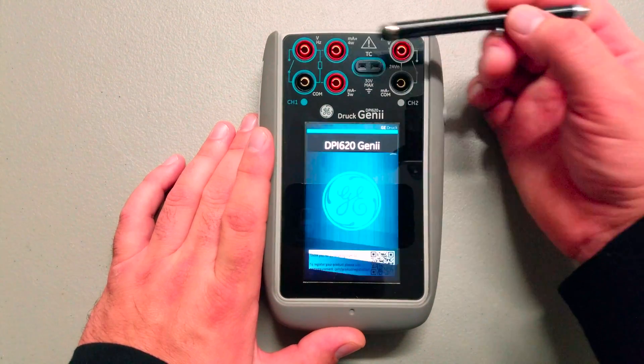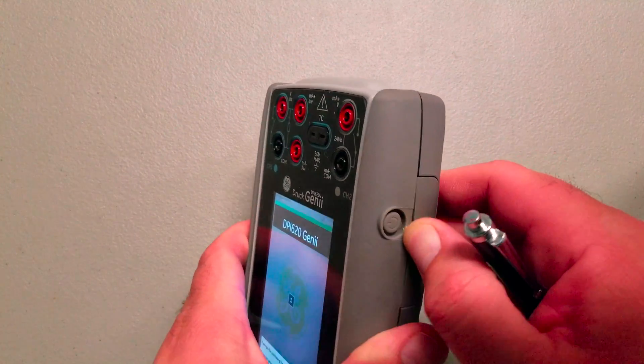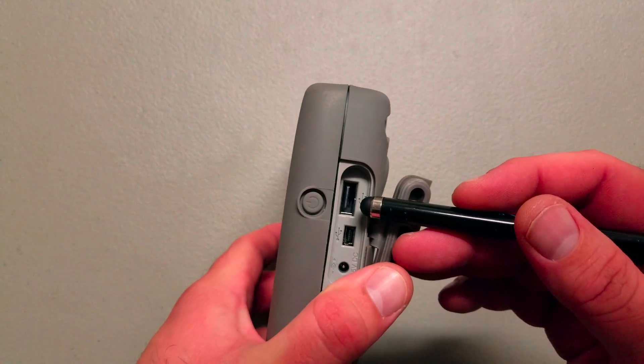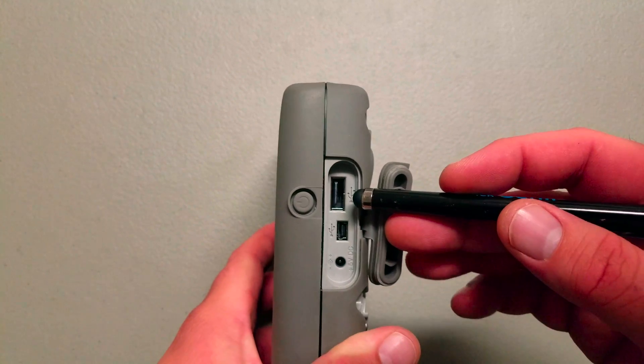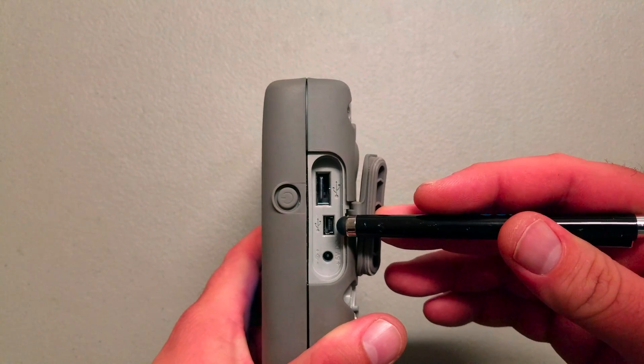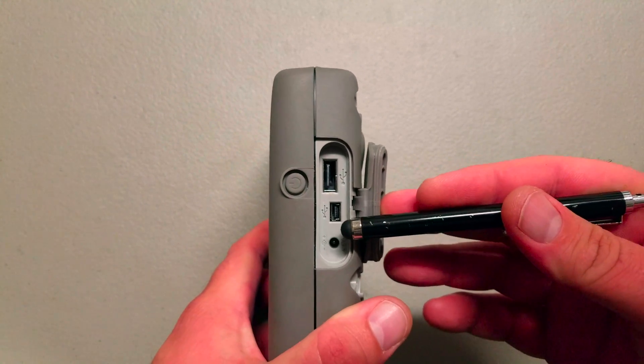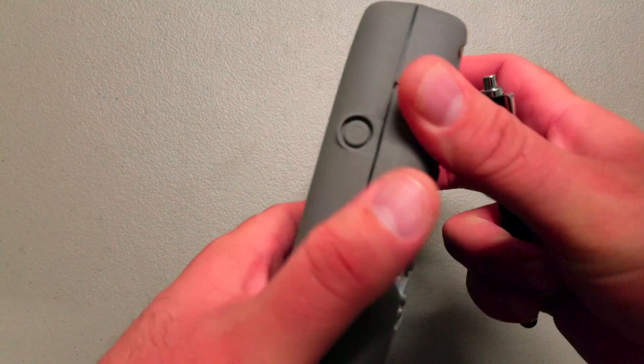Channel one is typically your read channel and channel two is typically your sourcing channel. It does supply 24 volts, it is battery powered, it is rechargeable. It has a USB host port for hosting USB thumb drives — this is where you'll do most of your updating. It has a USB client port for becoming itself a USB thumb drive, transferring files and communications, and of course the charging port — all behind this pretty rugged little flap here.